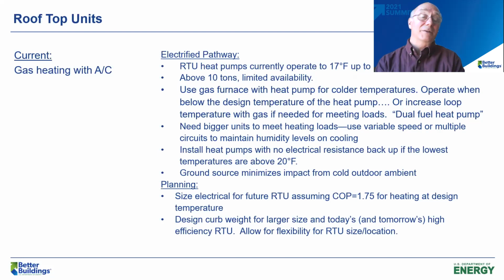Well, think about what happens on the heating side, where you're challenging that same piece of equipment, those same heat exchangers, those same compressors. Instead of being a 25 to 30 degree delta T, you might need a 70 to 75 degree delta T on a design day. And that actually makes all of the equipment larger in order to meet that heat pump load, especially if you're striving to do it all with heat pumps. It's pretty easy to think about heat pumps if you know that the temperatures won't drop below 20 degrees Fahrenheit. Now, that does not work in most of the cold climates, and as advertised, we wanted to talk about cold climates here. But certainly if you have facilities that are in other climates, really think about whether you can use a heat pump, especially if you're trying to pilot the technology, learn about the technology, get more familiar with it. Start with a climate zone where you have good confidence that it's going to be effective.